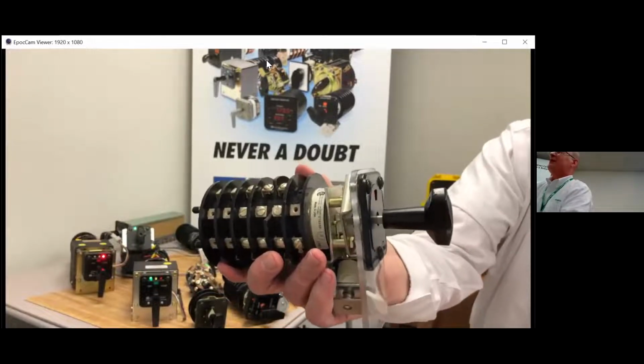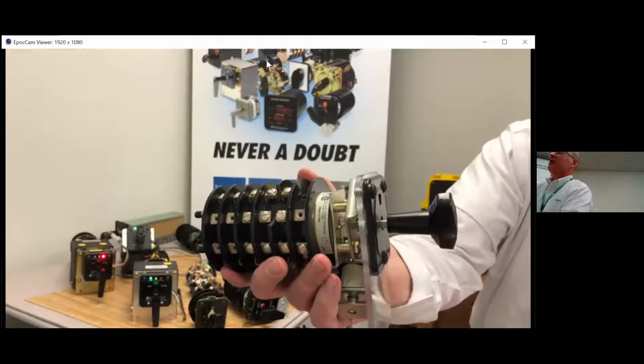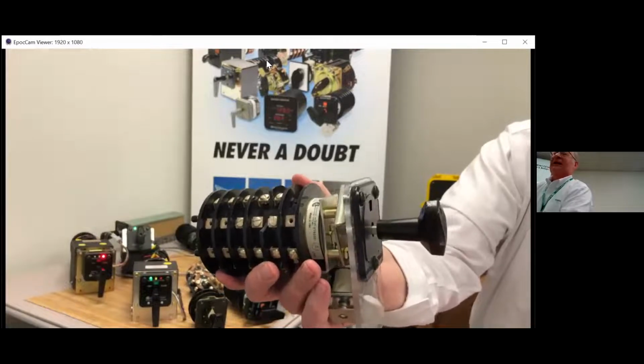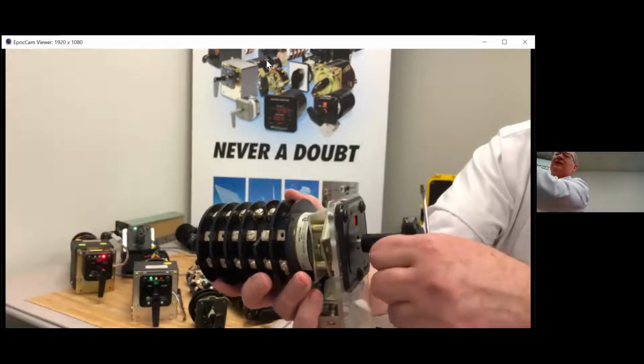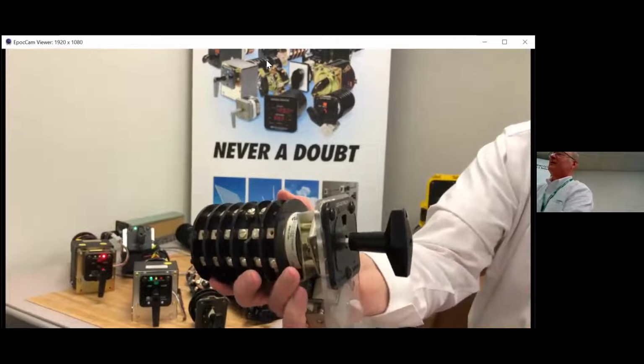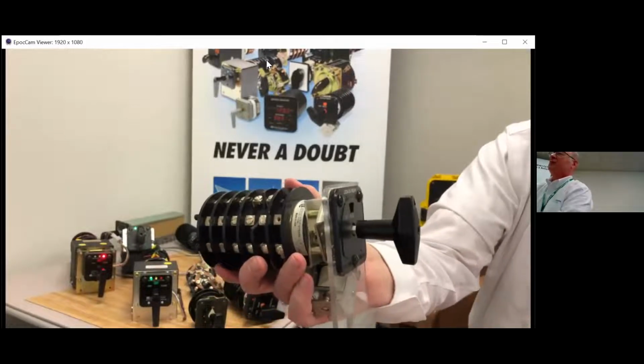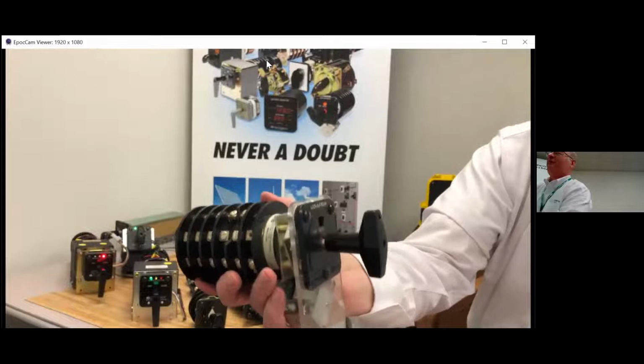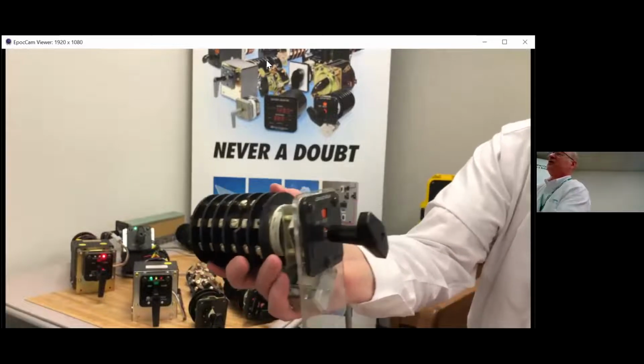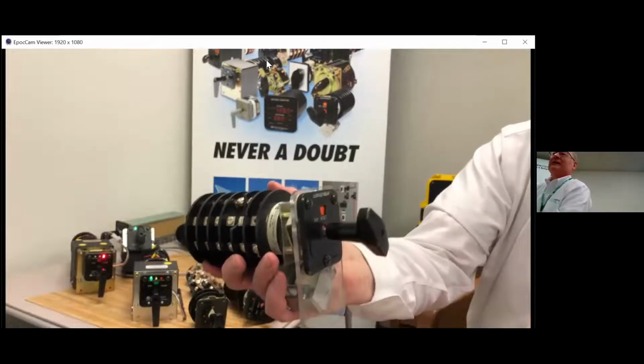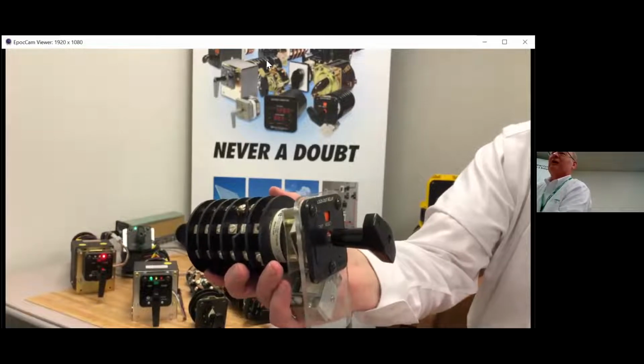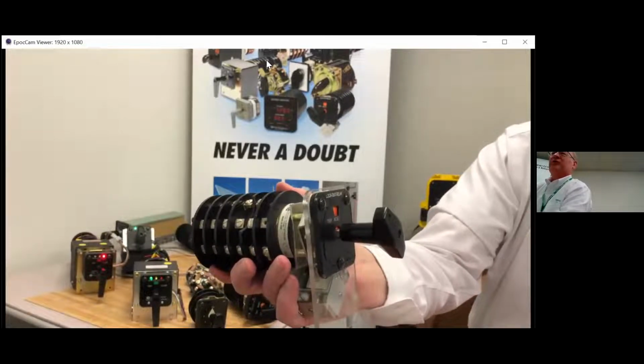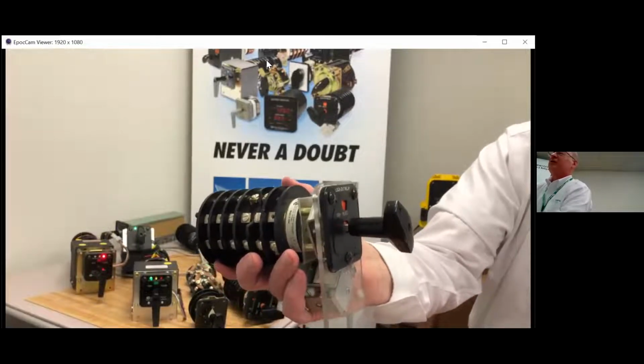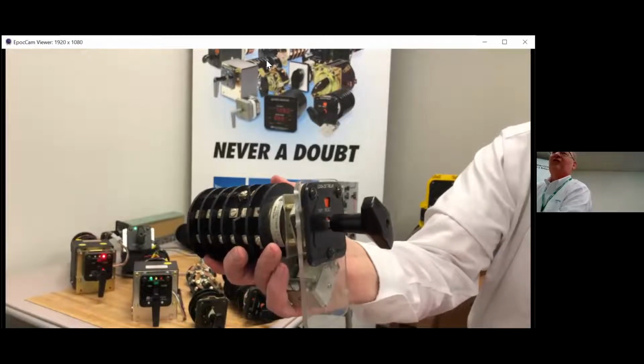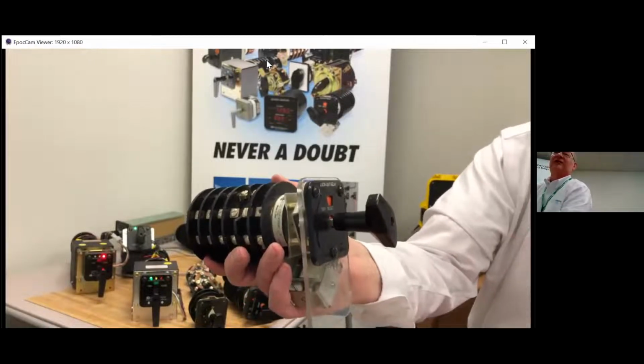And once that trips, you do not want to go back and just manually reset this switch, because what's going to happen is you're going to have your trip function there and it's going to trip it again. So if you think about it, you want to make sure you go out there and troubleshoot your circuit and all the circuits associated with that to find the fault before you reset this device.